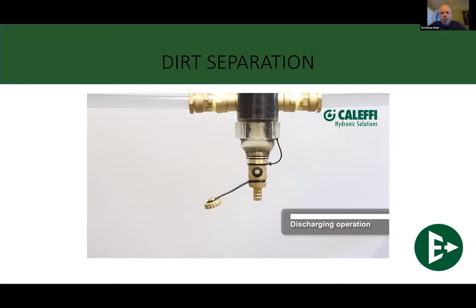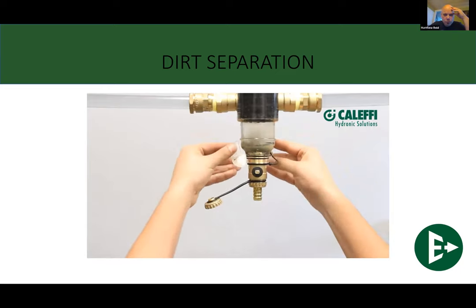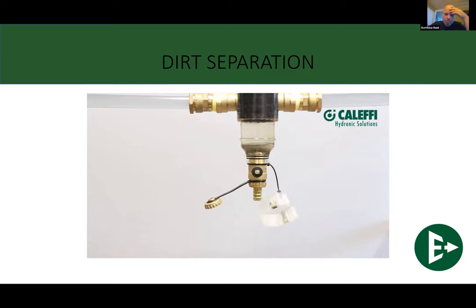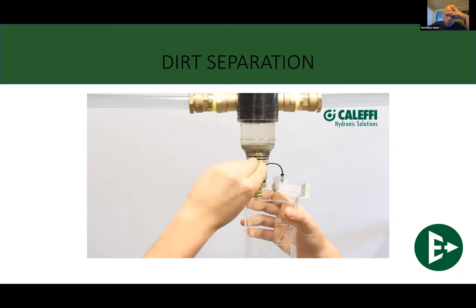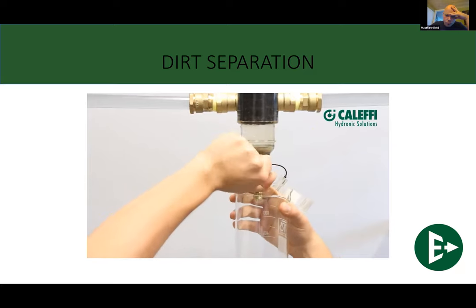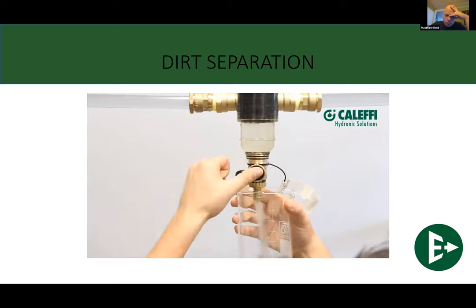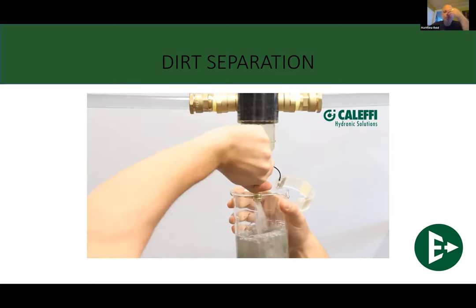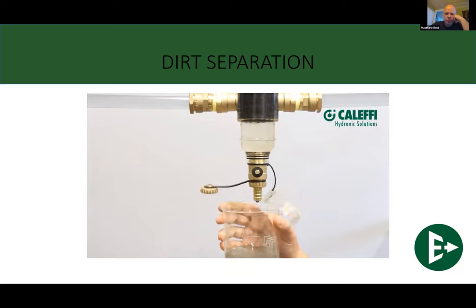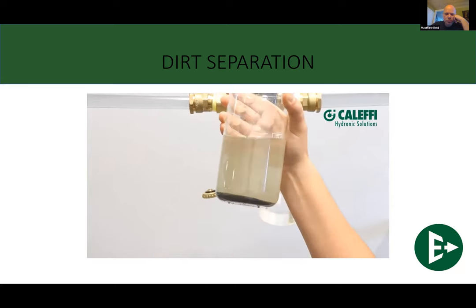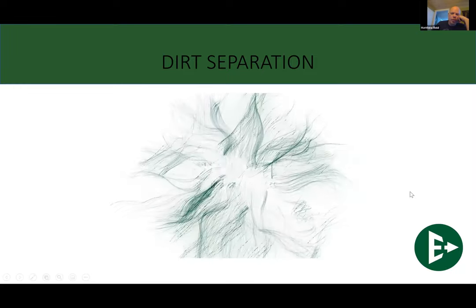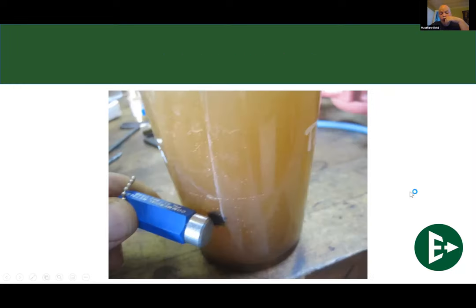So we've stopped flow to the system. We're going to do a discharge. Magnetite falls to the bottom. Flush it till the water goes clear. That's it. That's how a magnetic dirt separator works.